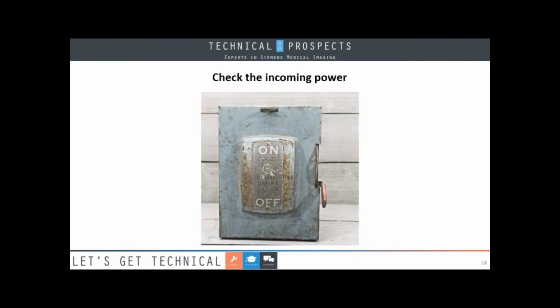Most of these systems have 3 AC lines, a ground, and a neutral. So you could have power to the cabinet, but you might have a leg drop out. It's more likely that you have a neutral line issue. I've seen neutral lines that were held on by a screw, and they were either loose or they came off completely. I once had a neutral line with 45 volts on it. A neutral or ground issue will cause a lot of bizarre issues, including tubes wearing out prematurely. So measure them. It won't take that long, and you might be surprised at what you find.